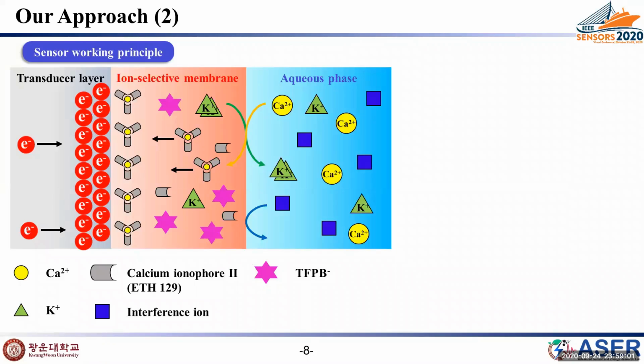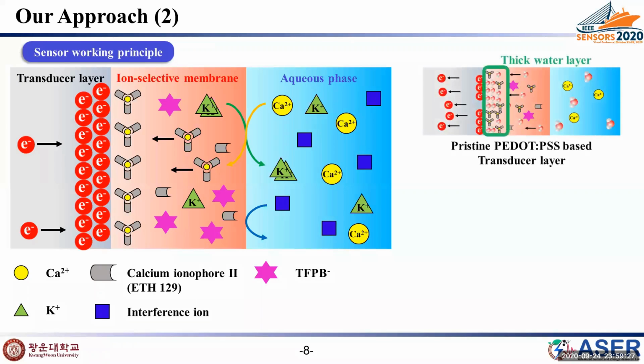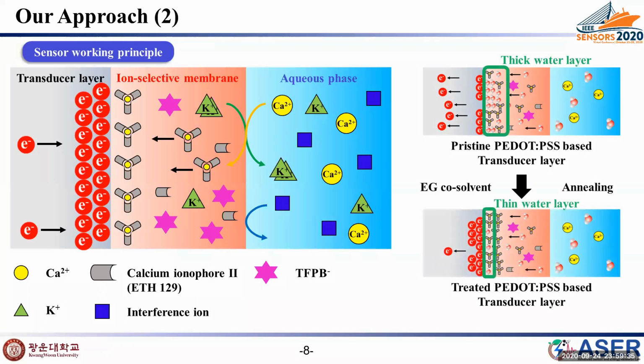The calcium ions in the analyte and the potassium ions in the membrane are exchanged at the interface between the ISM and the analyte. Then the calcium ion forms a complex with the calcium ionophore and moves to the transducer layer. At this time, an electric potential is formed across the total ISE, and the potential difference with the reference electrode is output. After that, a water layer gradually forms over time, but this can be suppressed by using our approach, resulting in improved stability with a thin water layer.